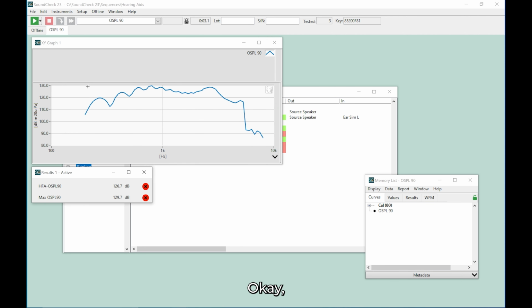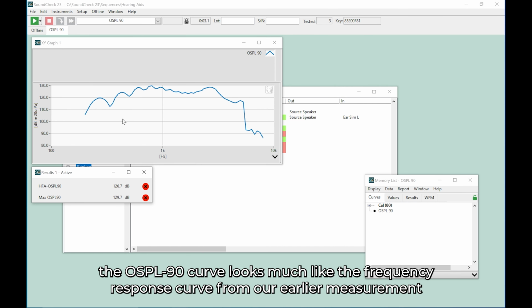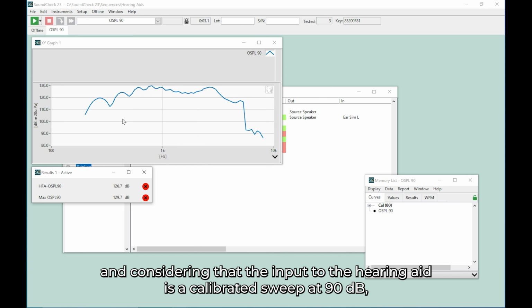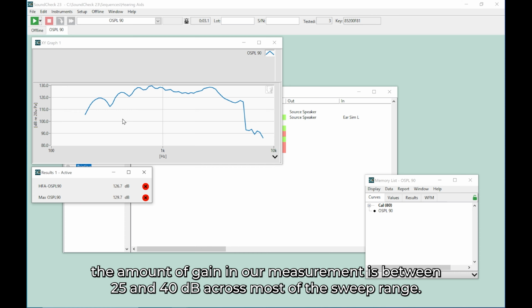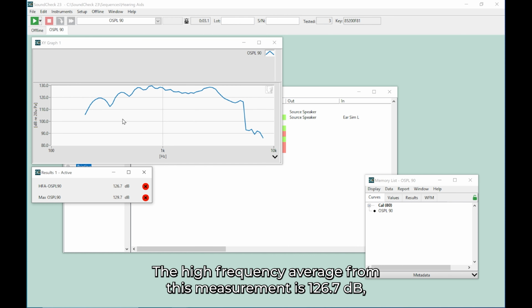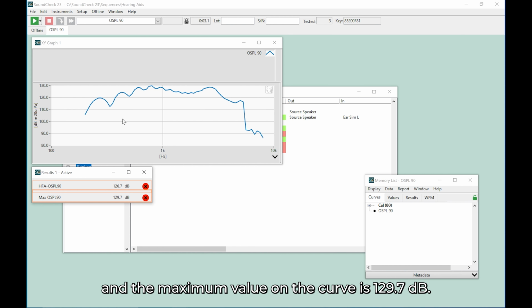Okay. The OSPL90 curve looks much like the frequency response curve from our earlier measurement, and considering that the input to the hearing aid is a calibrated sweep at 90 dB, the amount of gain in our measurement is between 25 and 40 dB across most of the sweep range. The high frequency average from this measurement is 126.7 dB, and the maximum value on the curve is 129.7 dB.